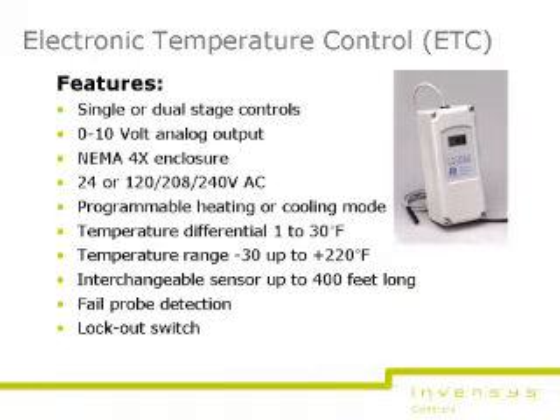1. Factory selectable single-stage or dual-stage control available with both normally open and normally closed outputs. 2. Factory selectable 120 or 240 volts AC at 50 or 60 Hz. 24-volt models are also available. 3. Temperature differential from 1 to 30 degrees Fahrenheit as set by the user. 4. Each model controls temperature ranges from -30 to +220 degrees Fahrenheit. And 5. Microcontroller diagnostics, including failed probe detection.